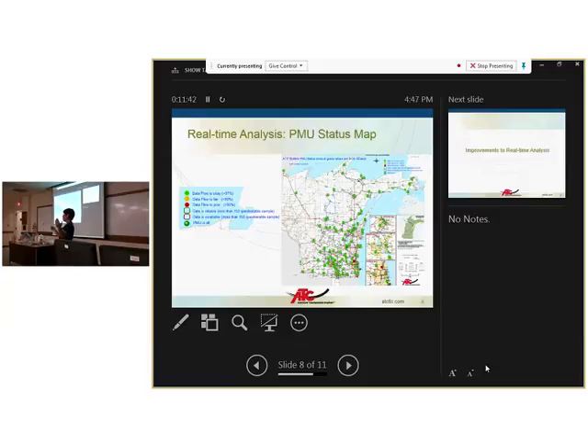The way PMUs work is you have a PMU and a PDC. The PDC takes all the data from a PMU and concentrates it in one place. If the data actually goes to the PDC correctly, then the data flow is okay. If the data shows lost time sync or some weird data, then it's unreliable data.